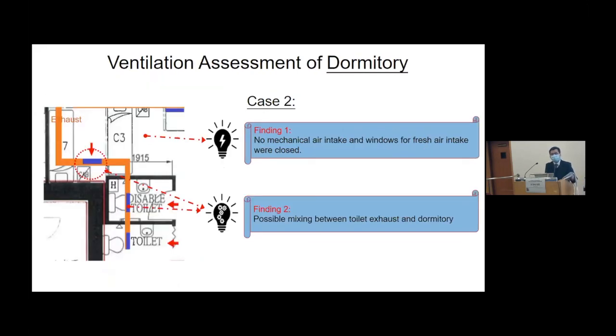In the second case, there was no mechanical air intake to the dormitory, but only mechanical exhaust ductwork. The design relies on fresh air being pulled into the dormitory via building gaps and openable windows. However, most of the windows were found closed and fresh air could hardly be pulled in. It was also noted that the toilet exhaust passed through the exhaust opening in the bedroom, which is right here, making a possible mix between toilet exhaust and bedroom as shown in the figure.